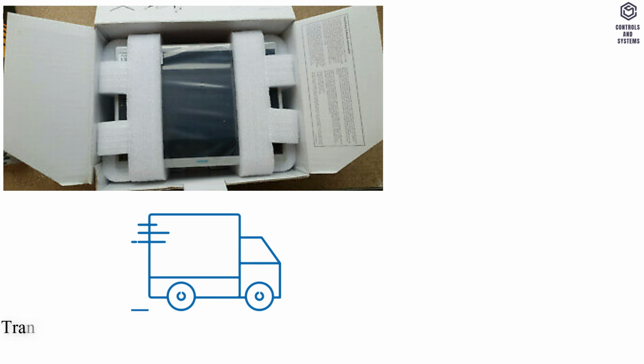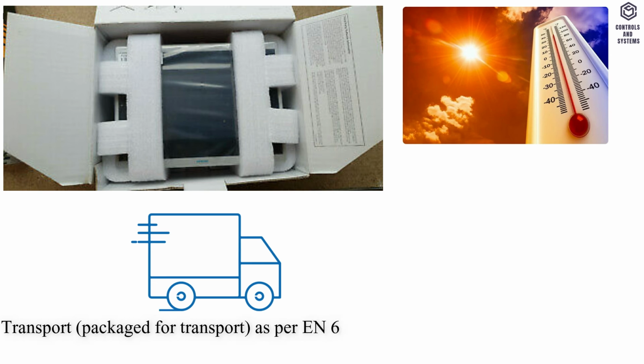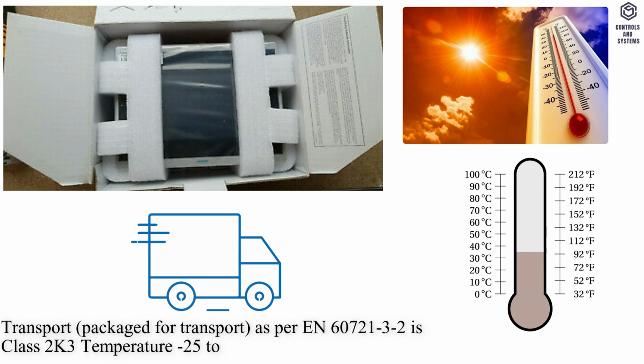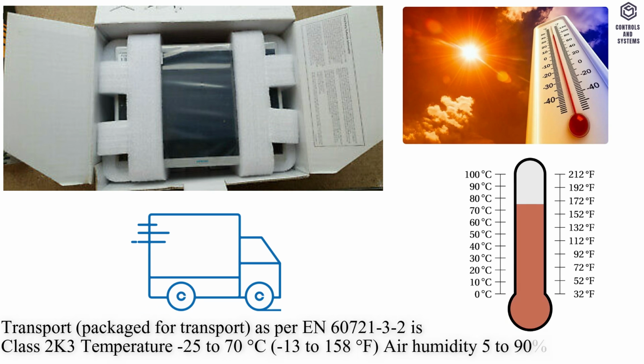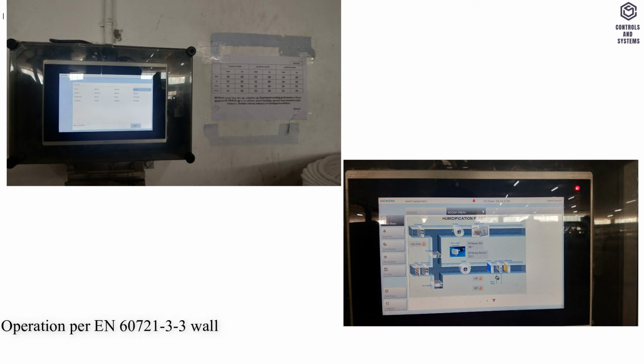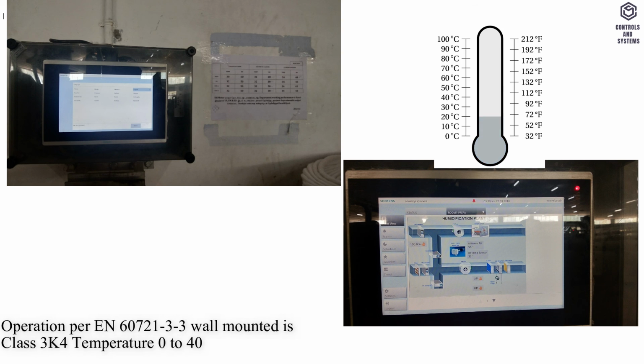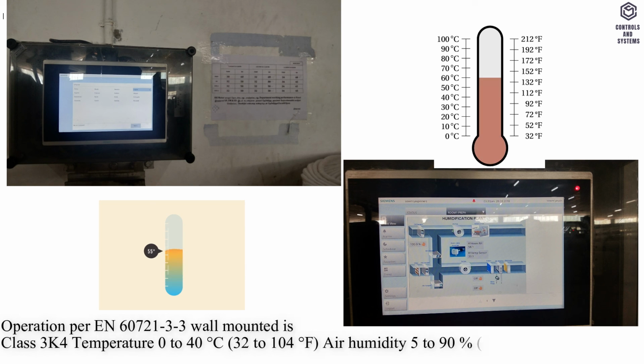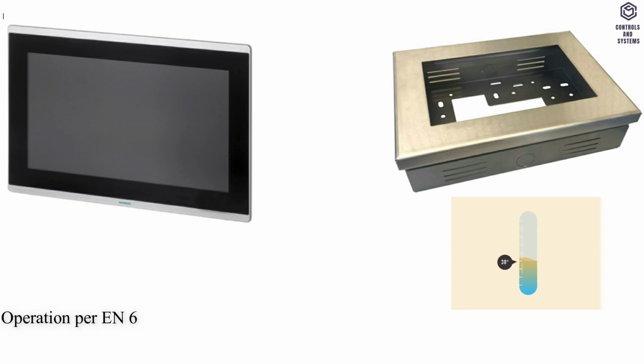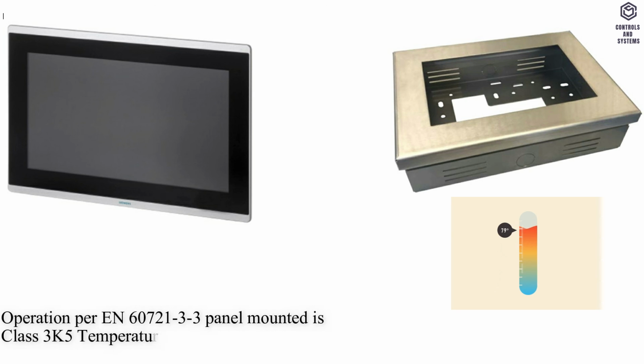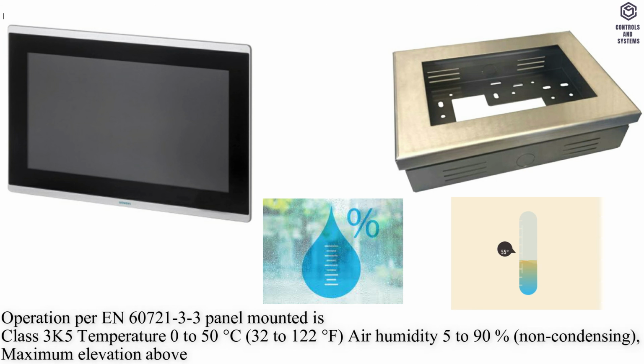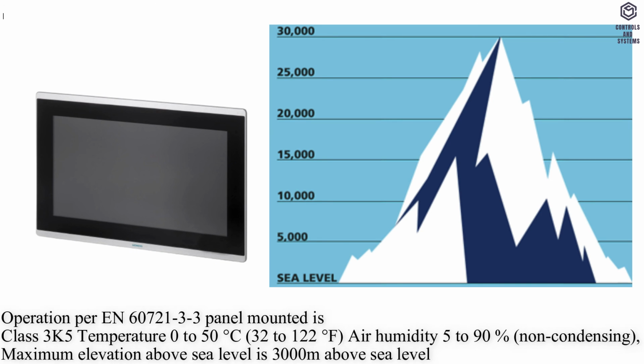Ambient conditions. Transport, packaged for transport, as per EN 60721-3-2 is Class 2K3, temperature -25 to 70 degrees Celsius, -13 to 158 degrees Fahrenheit, air humidity 5 to 90%. Operation per EN 60721-3-3 wall mounted is Class 3K4, temperature 0 to 40 degrees Celsius, 32 to 104 degrees Fahrenheit, air humidity 5 to 90%, non-condensing. Operation per EN 60721-3-3 panel mounted is Class 3K5, temperature 0 to 50 degrees Celsius, 32 to 122 degrees Fahrenheit, air humidity 5 to 90%, non-condensing. Maximum elevation above sea level is 3,000 meters.